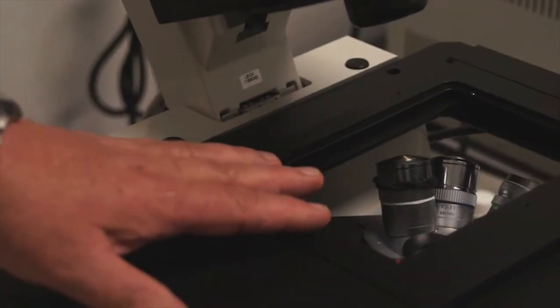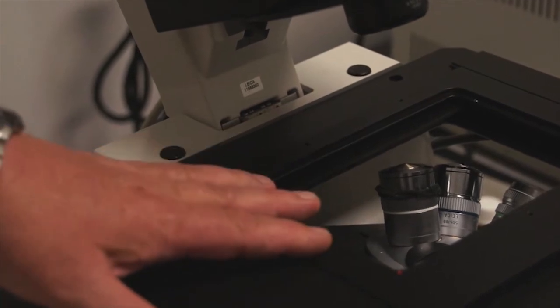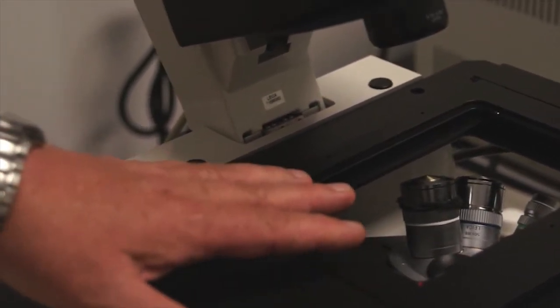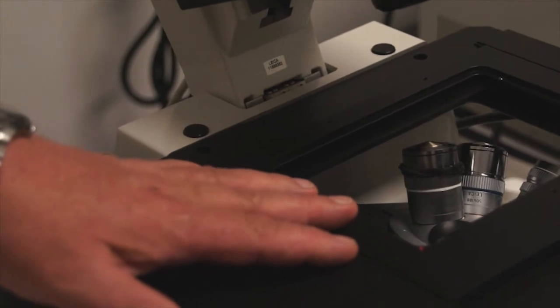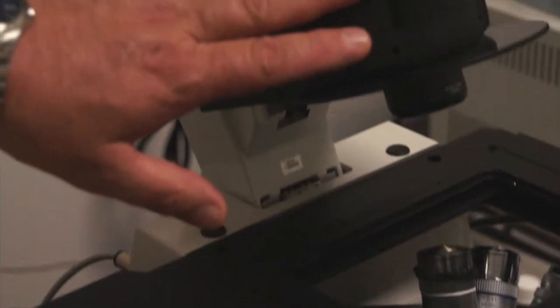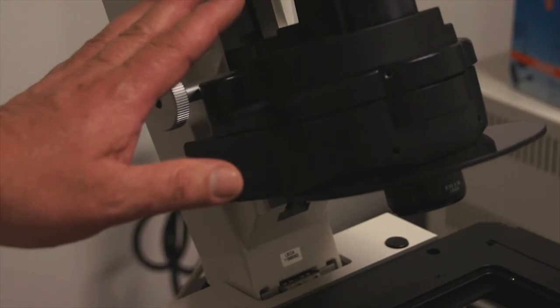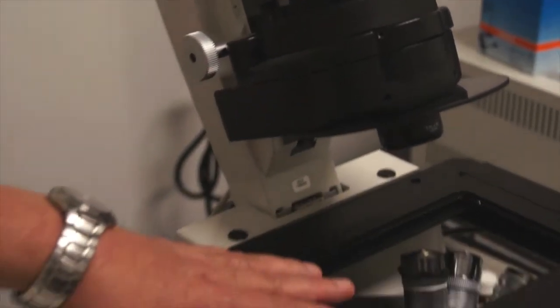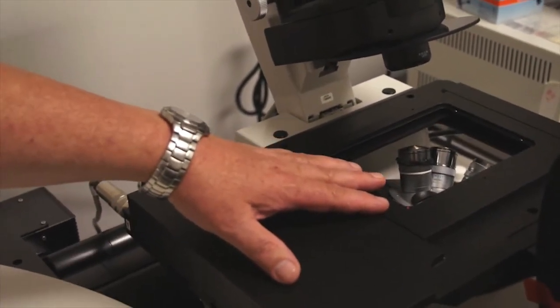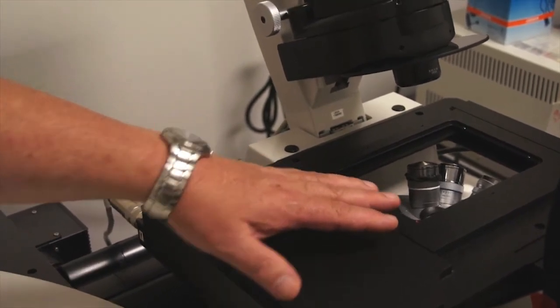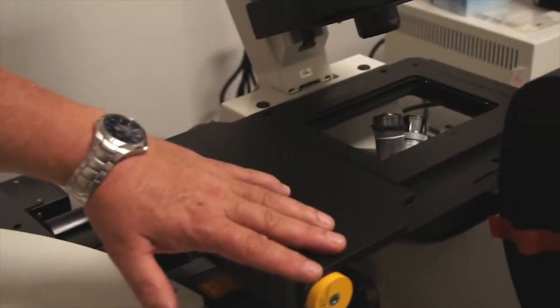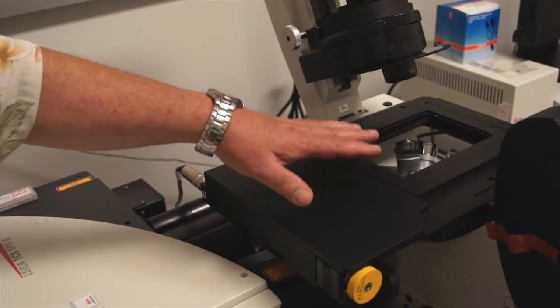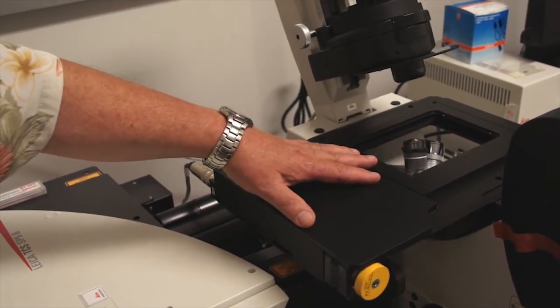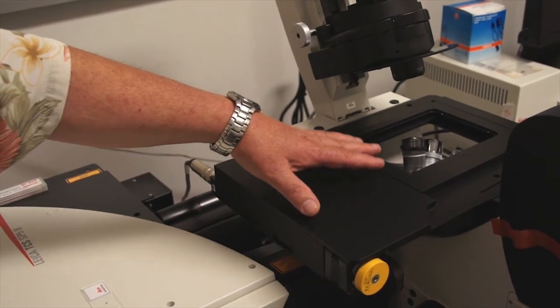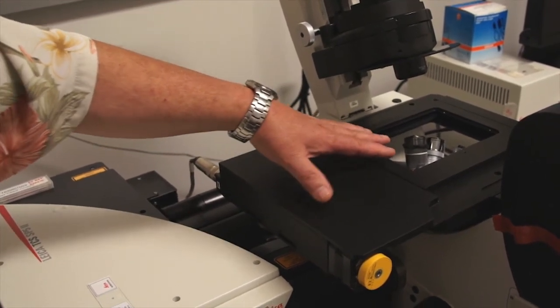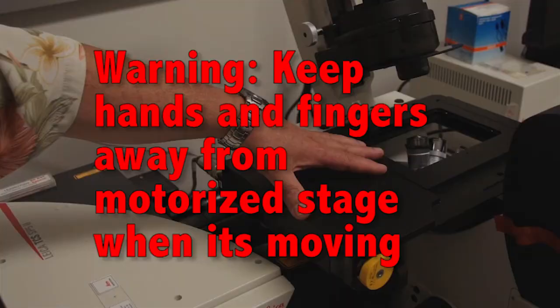The mechanical stage on the Leica microscope is motorized. There are motors that drive this stage in X and Y. And so that's another important reason why the condenser has to be rocked out of the way, because when you initialize the microscope, the computer will drive the stage in X and Y to its end point because of the motors that are on each axis of the stage. So be aware that this is a robotically controlled motorized stage which can injure your fingers. You could actually lose a finger if you put your hands in here while the stage is moving.